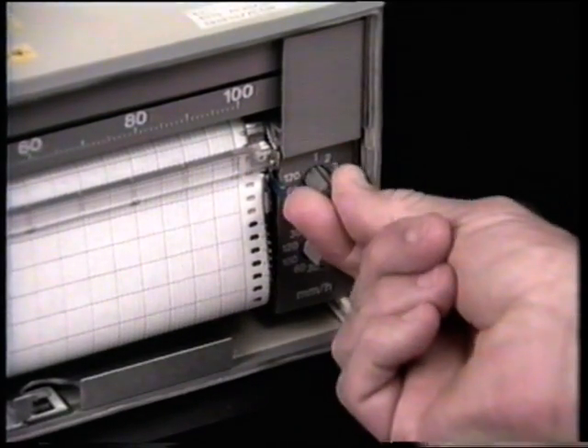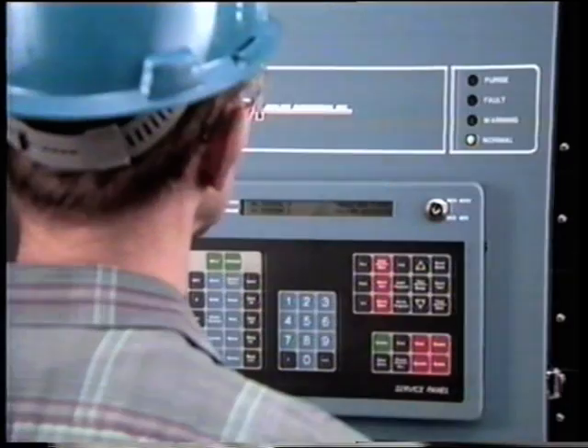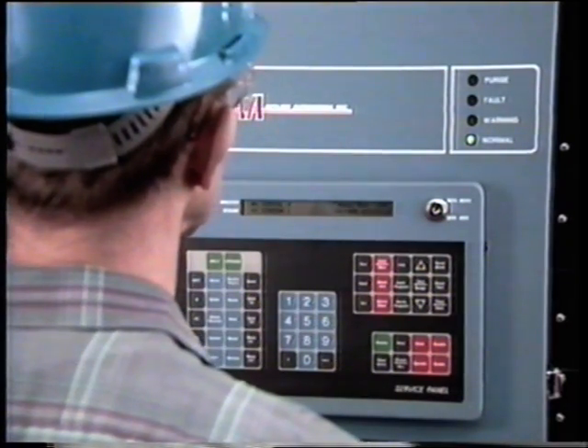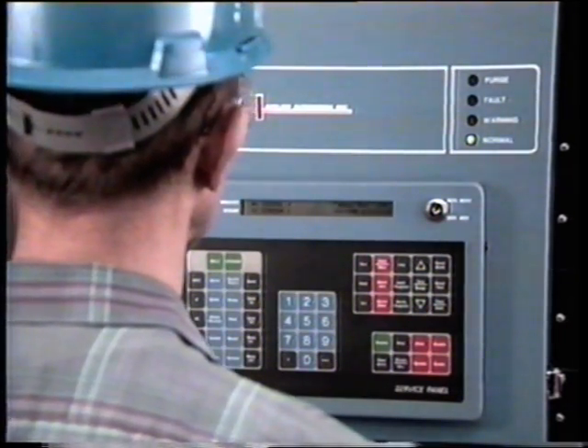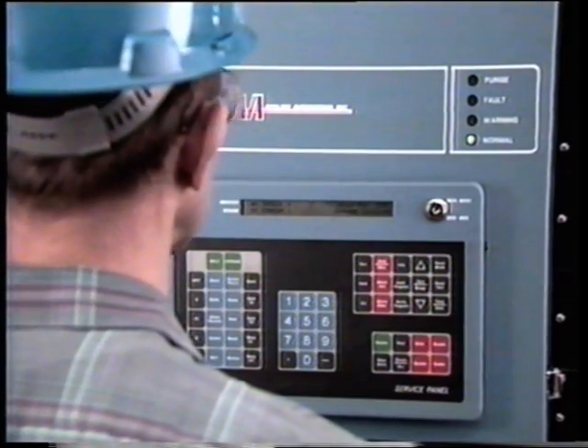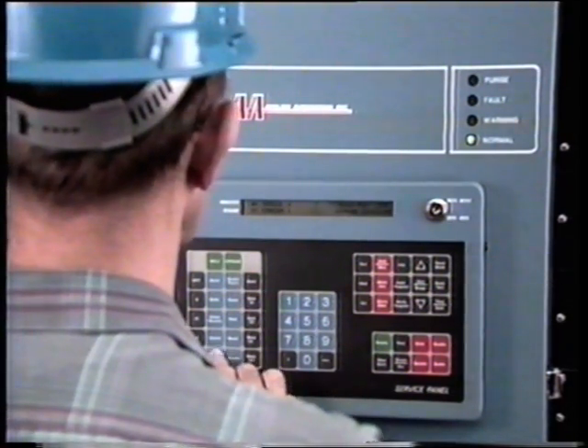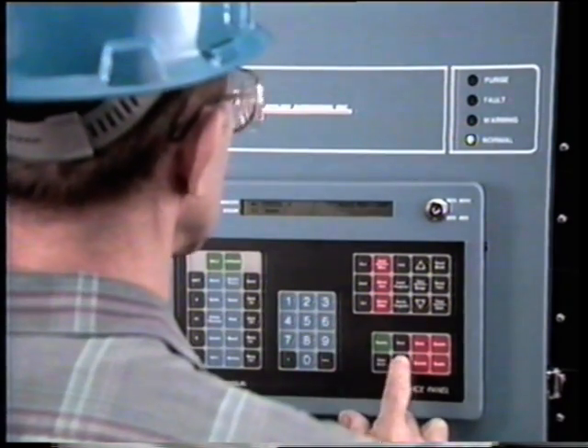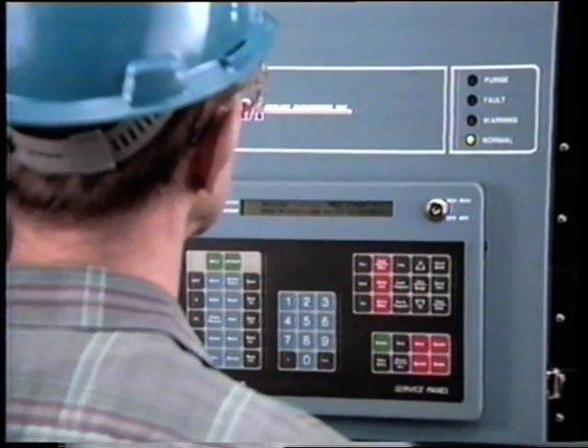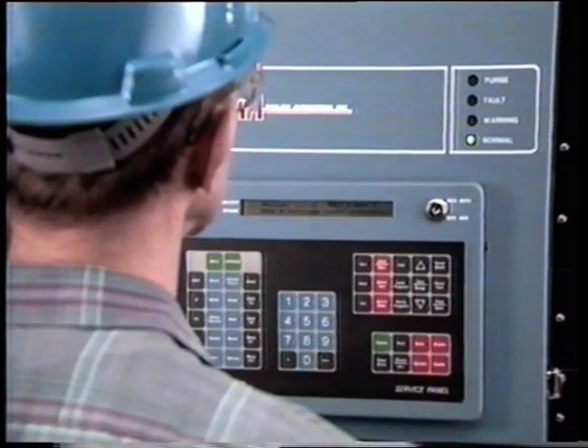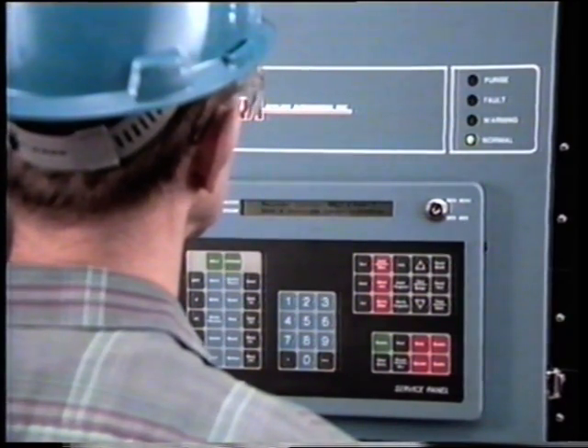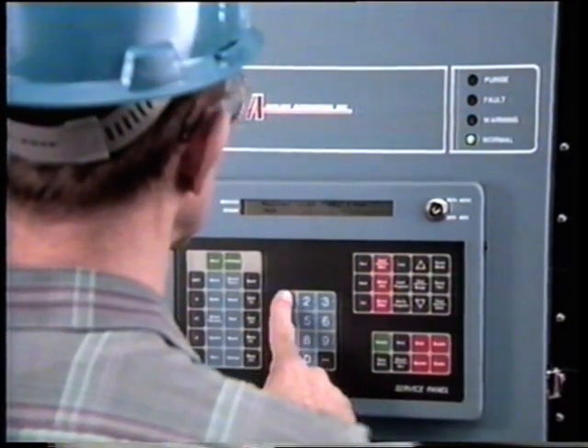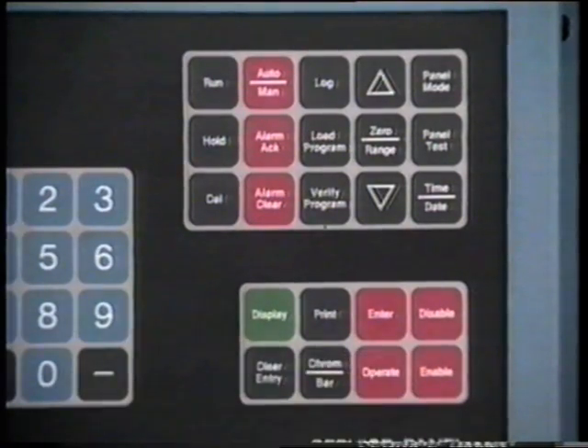Make necessary adjustments to the chart recorder. Select the chromatogram output on the recorder from detector 1. This is normally the main detector. To do this, press detector 1 and chromatogram bar graph on the service panel. Balance the detector by pressing Enter 1, 5, and Operate.